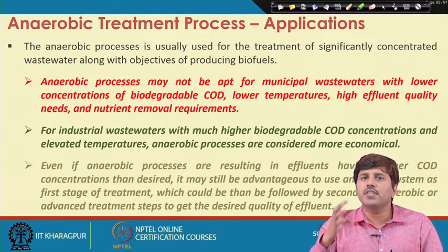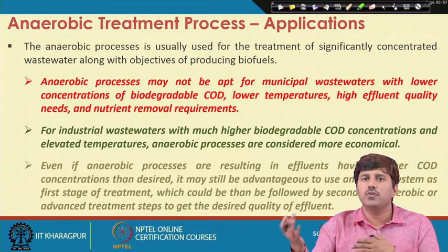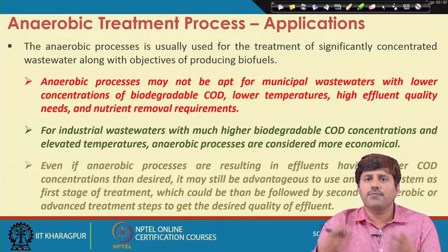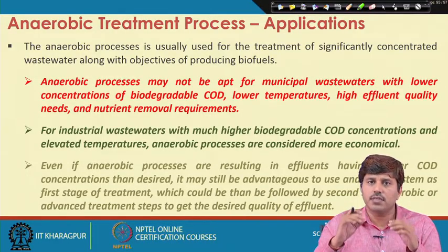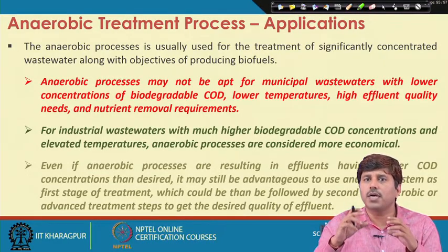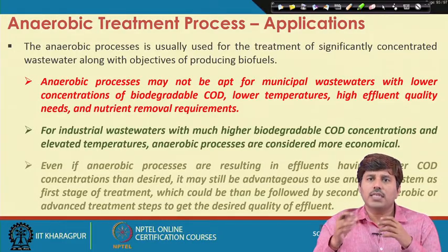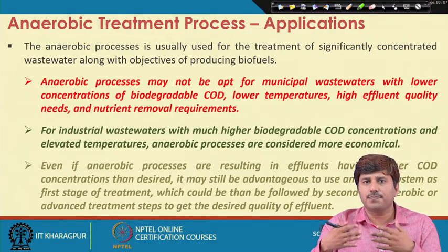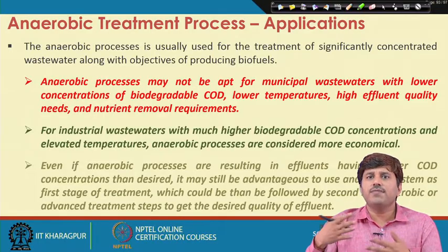So, the retention of this biomass is difficult, and as a result we may see that biomass getting washed out with the effluent. So, we end up losing biomass instead of producing biomass, and that becomes a problem, because if the reactor cannot sustain a sufficient amount of biomass, it cannot actually give you good treatment. Okay.